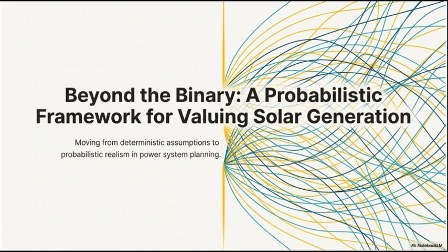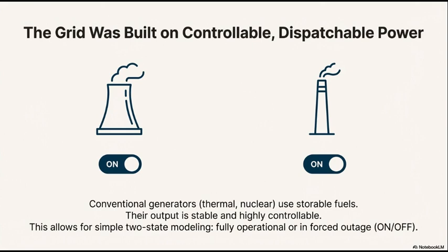The idea of the effective load model is quite elegant, but needs a little unpacking. If the generators are uncertain, why is the model focusing on the load? That's the genius of it. Instead of continually trying to calculate the varying output of thousands of generators, the ELM mathematically transfers the stochastic behavior, the outage probabilities of all those units, and shifts that uncertainty over to the demand side. Wait, so you're not saying the load itself is uncertain. You're saying the load plus the risk of generator failure is calculated together.